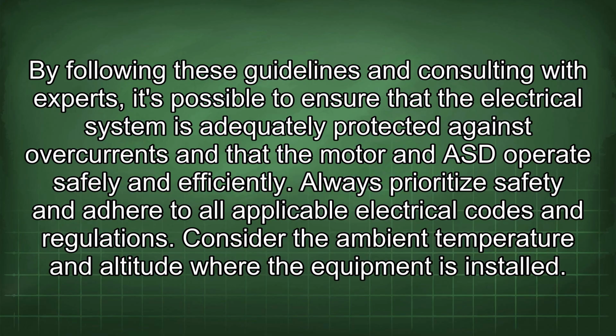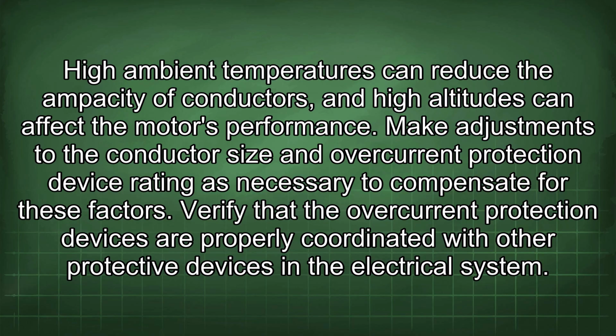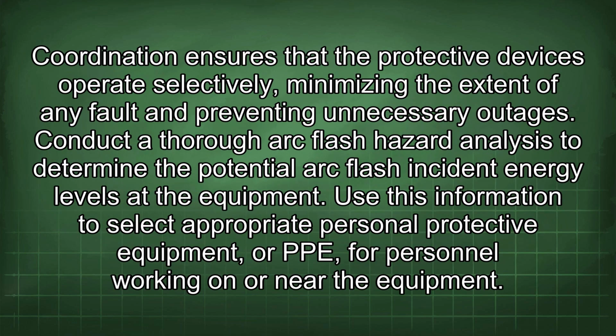Consider the ambient temperature and altitude where the equipment is installed. High ambient temperatures can reduce the ampacity of conductors, and high altitudes can affect the motor's performance. Make adjustments to the conductor size and overcurrent protection device rating as necessary to compensate for these factors. Verify that the overcurrent protection devices are properly coordinated with other protective devices in the electrical system. Coordination ensures that the protective devices operate selectively, minimizing the extent of any fault and preventing unnecessary outages.